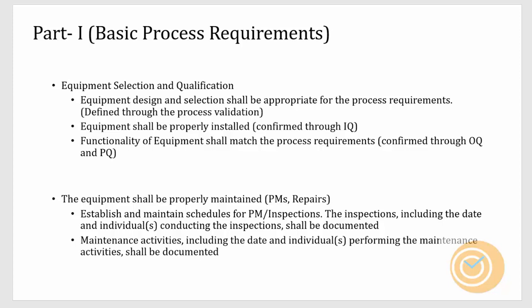That's what you would cover in your installation qualifications, to make sure that the utilities are available, the operating documents are available, and all the checklists that you would need for the installation qualifications are available. And you have to have the formal qualifications and report, which are covered in the installation qualifications.